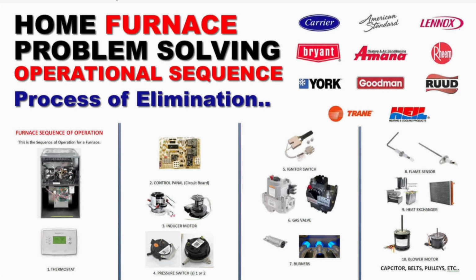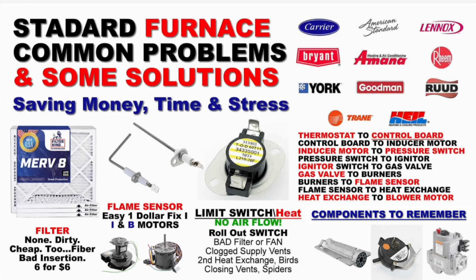If we looked at some of the common problems and possible solutions, I would have this in mind. So here's our recap of our sequence of operation. Biggest culprit for any of these things failing down the line is having a dirty filter, one that you don't change or you change 2 or 3 times a year. That's going to put stress on all of the other components inside your furnace. Furnace life is about 5 years before you have to start changing some of these components. So let's keep our filters clean, change them every other month. That's why they come in 6-packs.